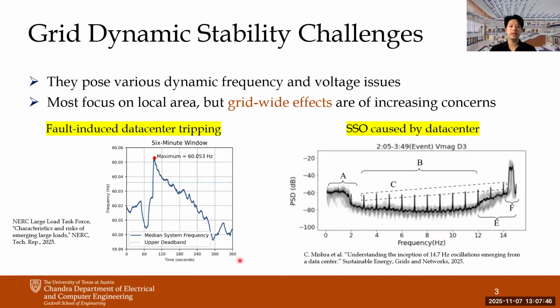In the case of data center tripping, if a fault occurs nearby, the data centers will trip from the grid due to lack of voltage ride-through capability. From the grid perspective, this could be seen as a ramping decrease of load, which eventually leads to an overfrequency problem in the wide area.